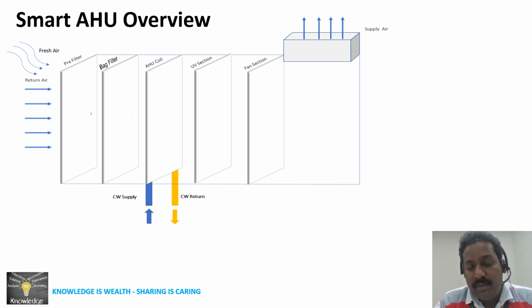In the current AHUs available in the market, the UV section is inbuilt. If it is not there, older HVAC setups can be easily retrofitted with a UV section. This is a very important norm. Even the ISHRAE standard says to retrofit with UV to improve the air quality, because UV inactivates the virus, bacteria, and fungus content in the air. After the UV section, the air passes to the fan section. In earlier days we used induction motors; now induction motors have been replaced with EC fan motors. After the EC fan, the air is supplied again to the field area.